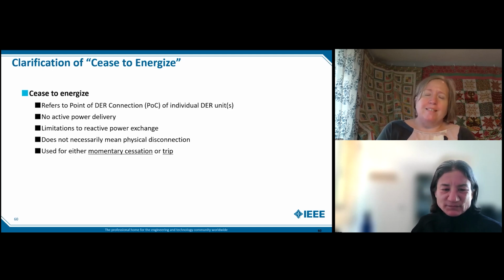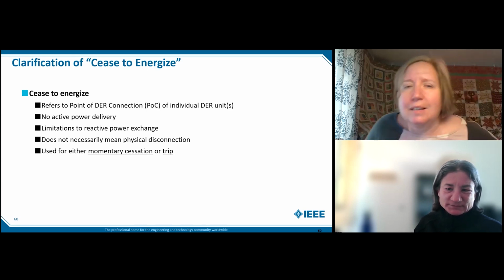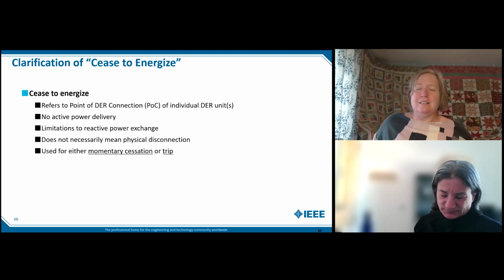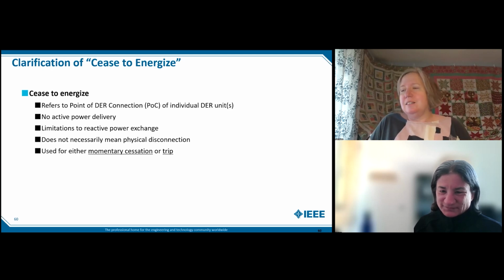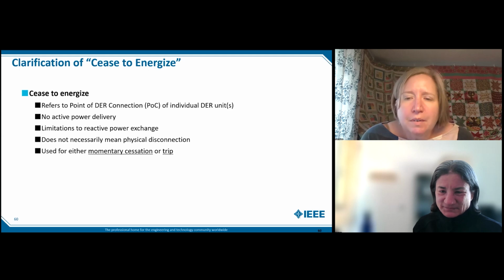Yep, this touches on a tension between island systems and the bulk grid. Jeanette, way back when, part of the argument for having confidence you're actually responding to a short circuit is, for extreme, even detectable deep dips at the project level, it indicates there's a bolted fault somewhere. If you're getting down to 0.2 per unit voltage, there's something big going on. On smaller systems, especially things like ground-related faults, on weak systems, you can't necessarily depend on a 0.8, 0.9 per unit voltage drop to tell you, okay, there's something major wrong.